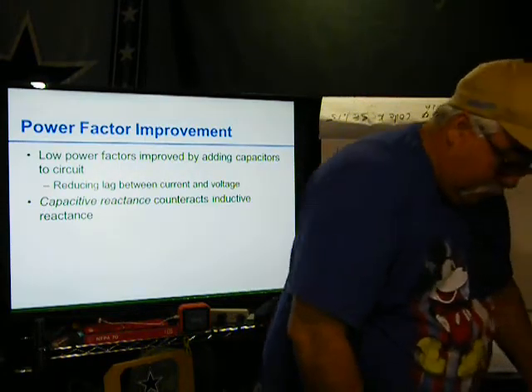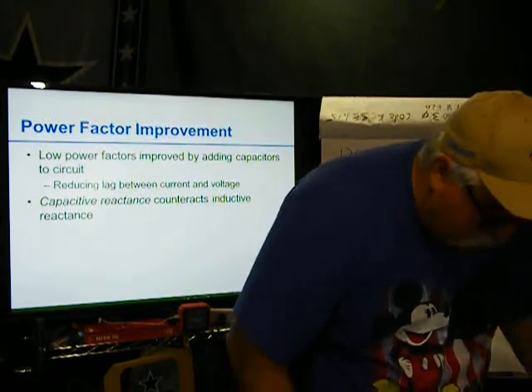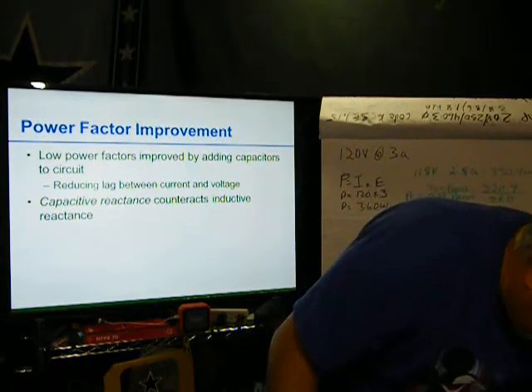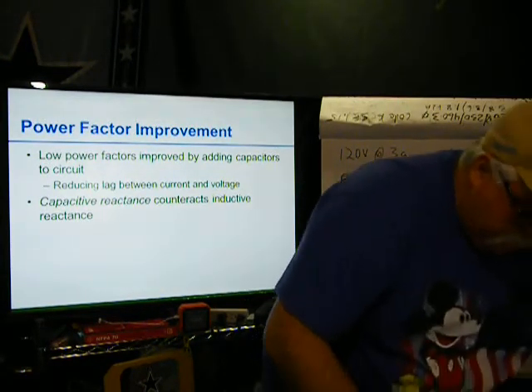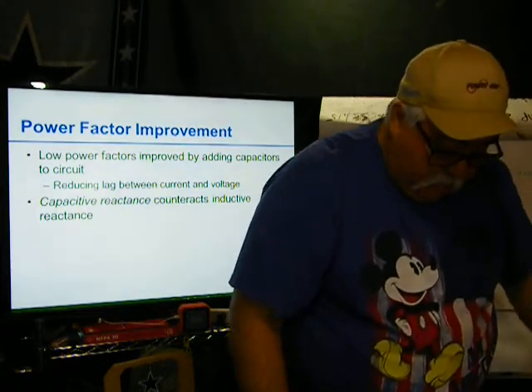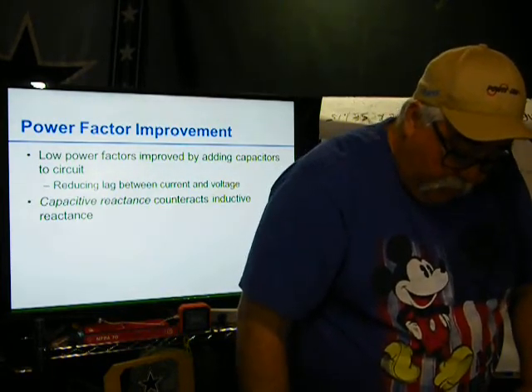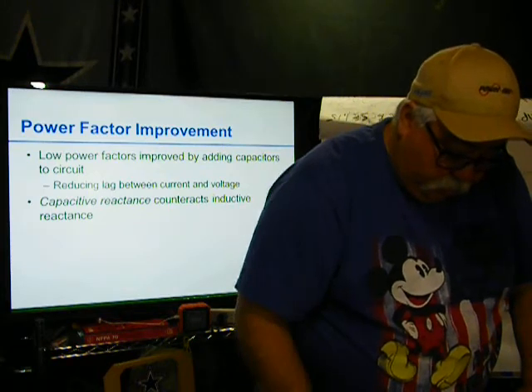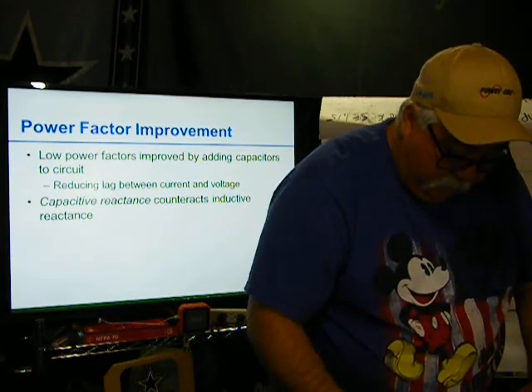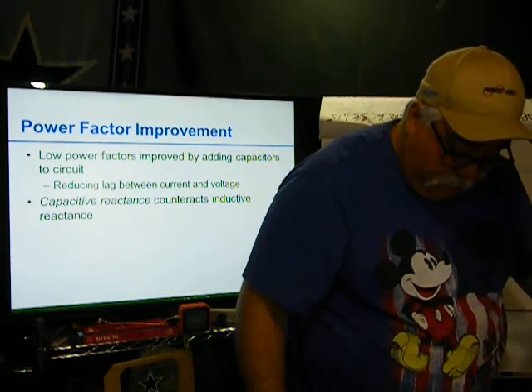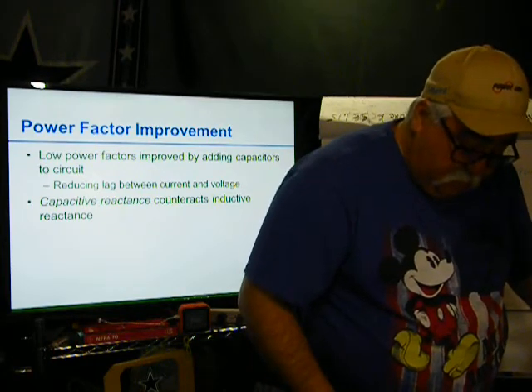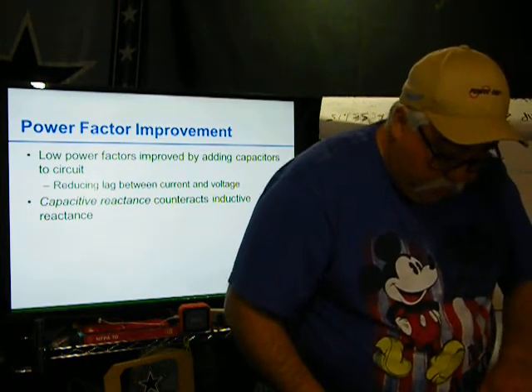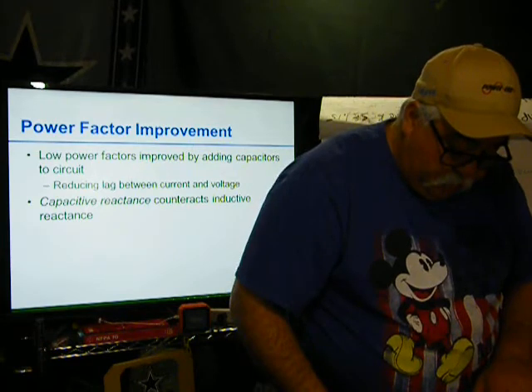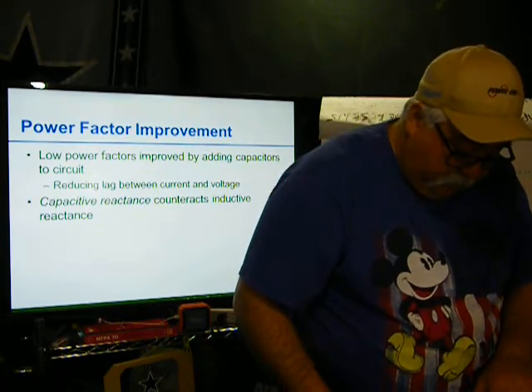Let me get my. So it says, ideally motor circuits would have a power factor of 1, however this is realistically unattainable. Low power factors can be improved by adding capacitance. This introduces capacitive reactance, which counteracts inductive reactance and improves the power factor.